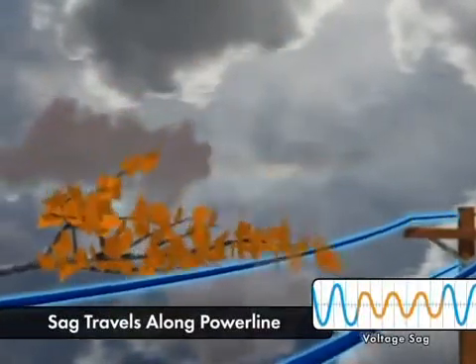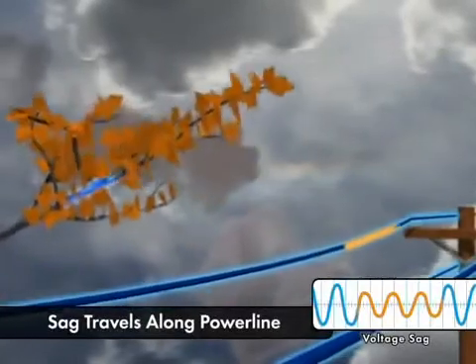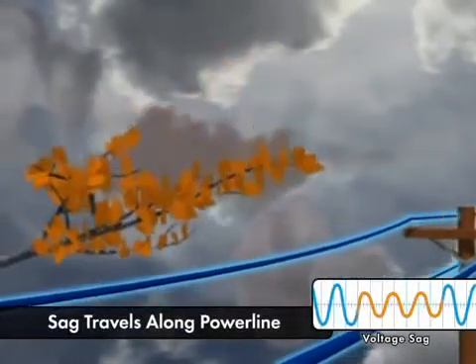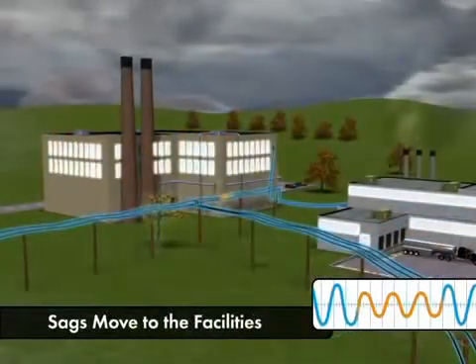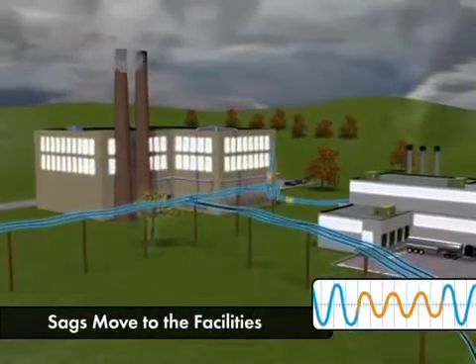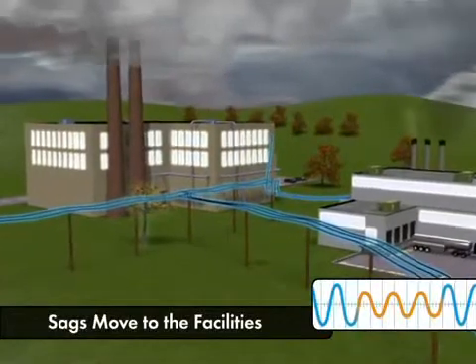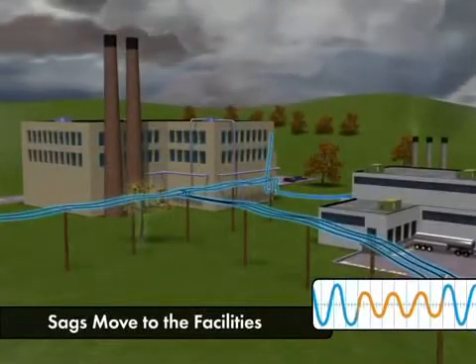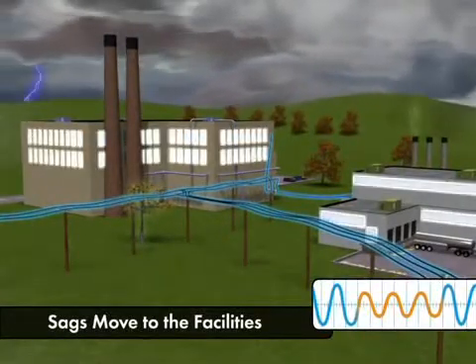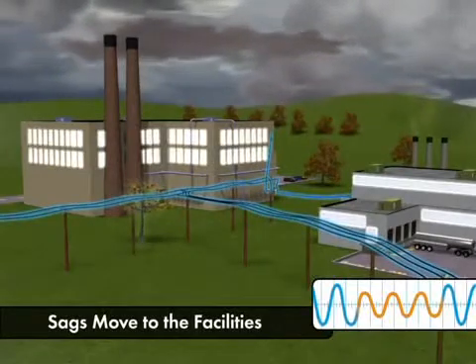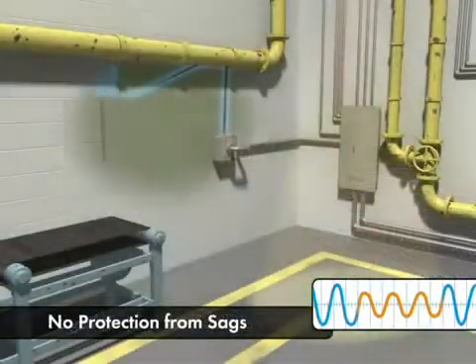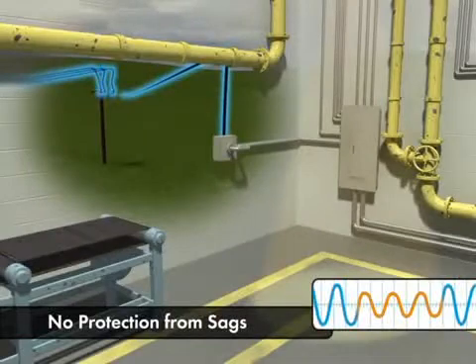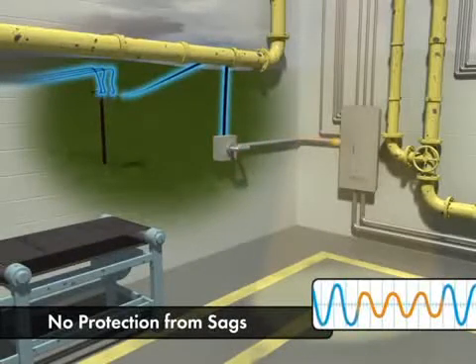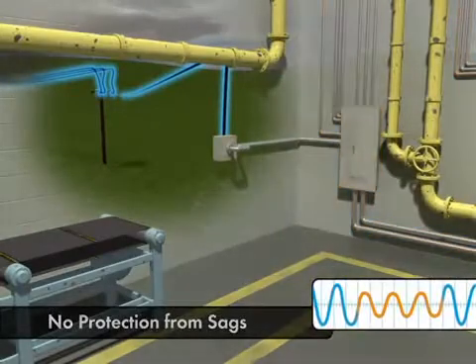Due to voltage contribution from parallel lines and some loads, the voltage appears at the facility as a sag. If the voltage event is longer than a few cycles, fuse or breaker operation would clear the fault and return the system to normal. Depending on the depth and duration of the voltage sag, sensitive electrical or electronic loads may be affected. Costly downtime, material scrap, production equipment damage, and product quality issues can be the result of sag events.